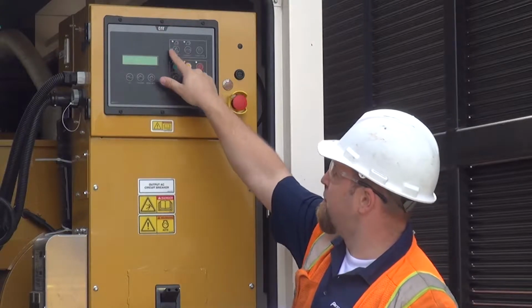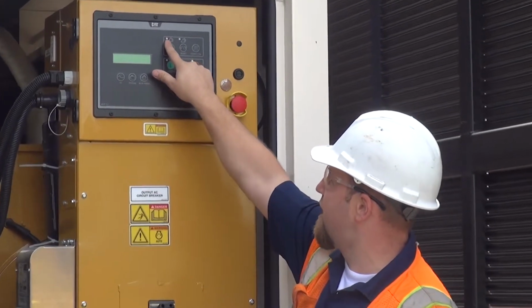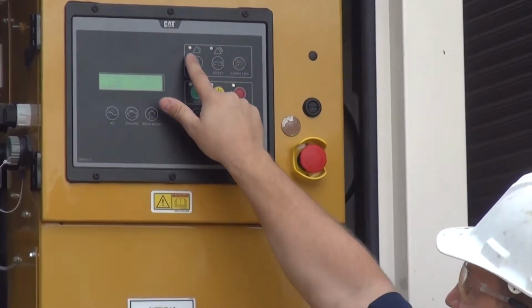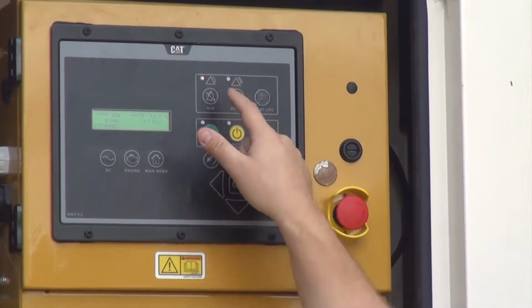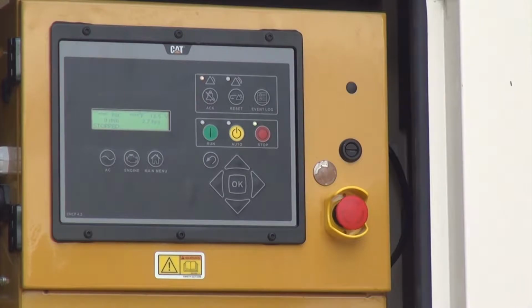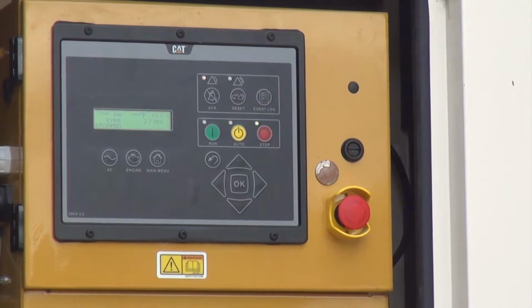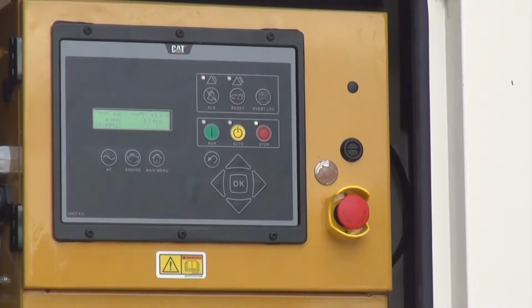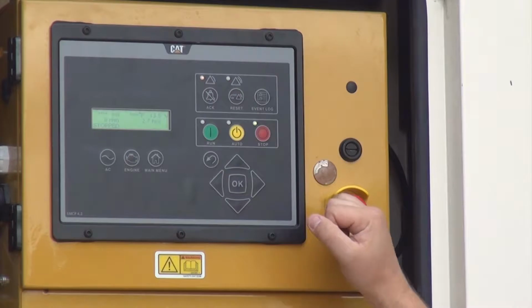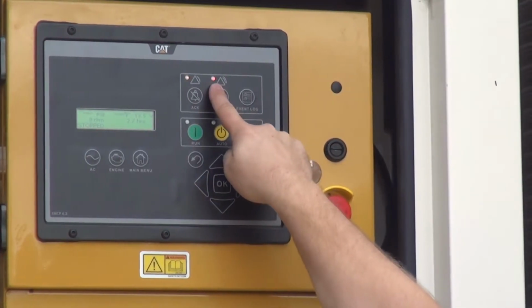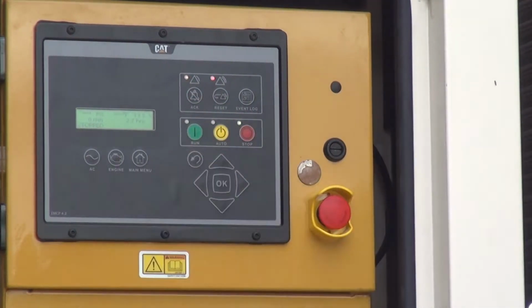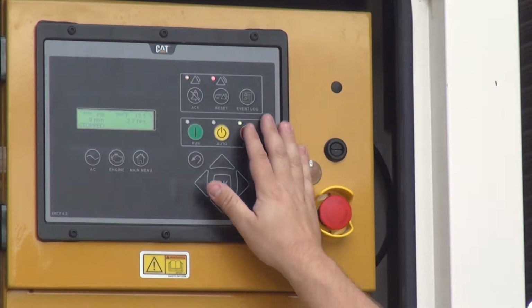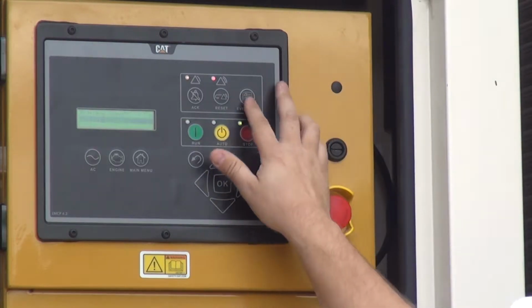The acknowledge button will silence it and let you know you have an alarm. There are two different lights here, a yellow and a red. Red is a hard shutdown, something that really protects itself -- low oil pressure, low coolant, overspeed, underspeed, high voltage, low voltage, a lot of different conditions where you could actually damage the engine or the generator will trigger a hard shutdown, and you'll see it light up red. Same thing, you acknowledge it. Now what I want you to notice here is this is the event log right here.